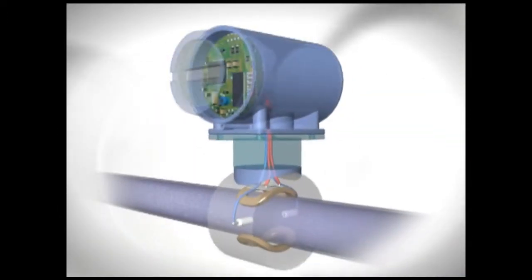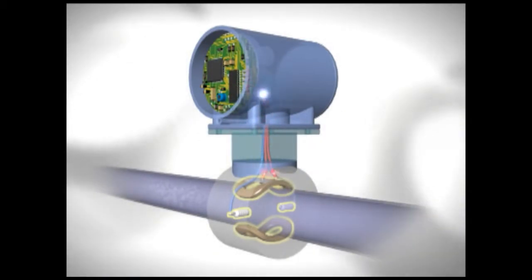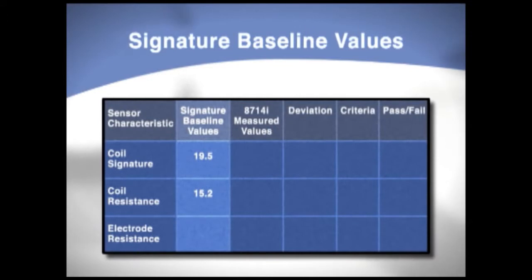Flow tube sensor calibration is verified in a similar manner. At the time of initial calibration, the 8714I establishes a flow tube sensor signature for the coil circuitry and electrode circuitry and stores that information in non-volatile memory. This establishes a baseline of the meter's magnetics.